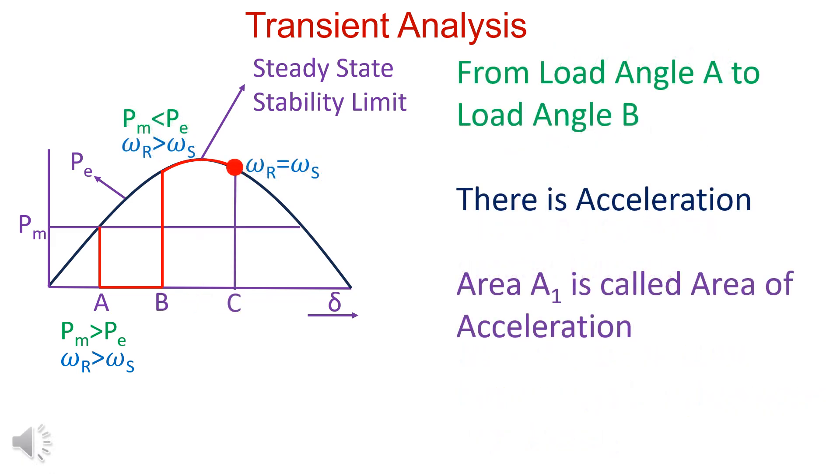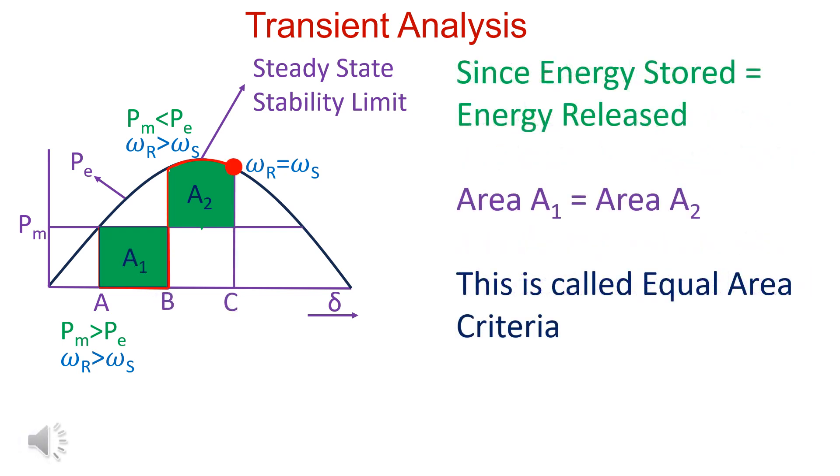From load angle A to B, there is acceleration. Area A1 is called area of acceleration. From load angle B to C, there is deceleration. Area A2 is called area of deceleration. During acceleration, surplus energy is stored in rotor. During deceleration, surplus energy is released. Since energy stored is equal to energy released, these areas A1 and A2 are equal. This is called equal area criteria.